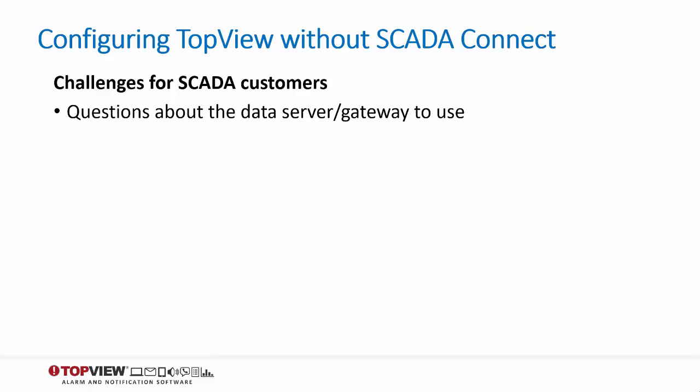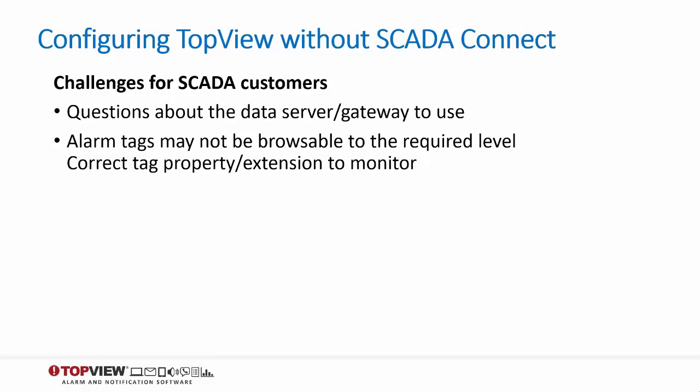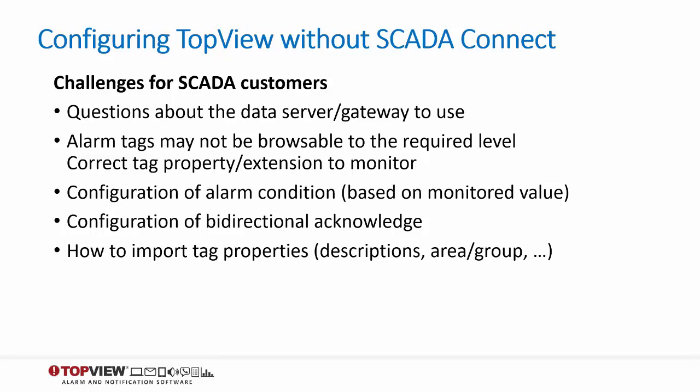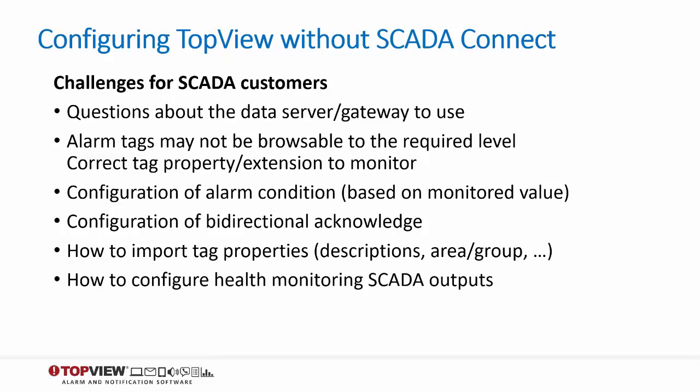First, the user must configure the gateway used to access the data server. The gateway is typically the OPC server for the SCADA, although some SCADAs have multiple OPC servers, or may require the user to perform configuration steps before clients like Top View can connect. Although tag browsing usually exists, many SCADAs do not expose the full alarm tag name with the correct extension or property required by Top View. Based on the data type of the alarm tag, the alarm condition must be configured correctly. For example, Boolean alarm tags will have an alarm condition of equals true, while some SCADAs require monitoring for a set of values or a specific bit of an integer value. For bi-directional acknowledge, the correct acknowledge tag names and acknowledge values need to be configured. Additional tag properties like alarm description, priority, and group must be imported. Optional health monitoring SCADA outputs also need to be configured.